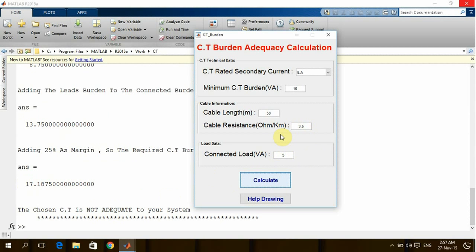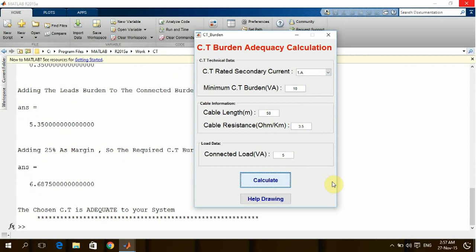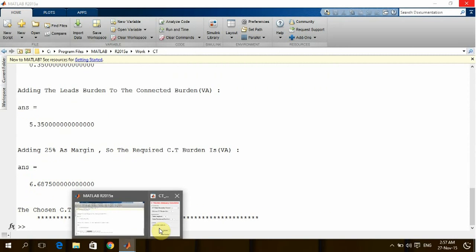Since the cross-section of the cable will be reflected commercially on the project, the design engineer can go back to the CT secondary current and choose rather than five amps to be one amp. Here we can see that the CT is adequate right now for the system.